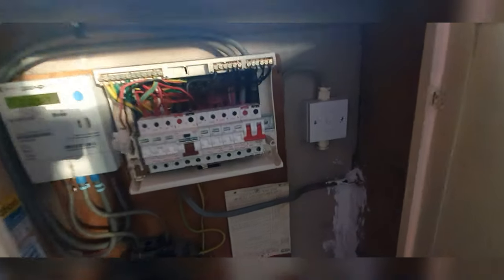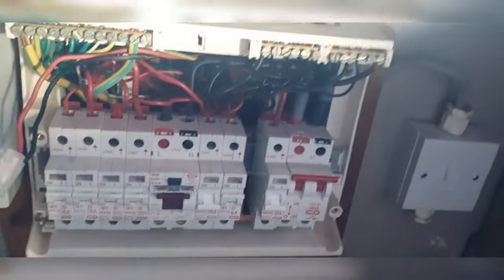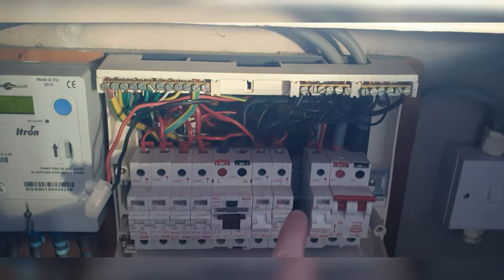There's not really much to show - that's going over there, problem solved. It's RCD protected - yay. So I've moved that over. They seem to have borrowed a neutral. I've moved that one over there now - so you've got your lights up and there's your lights down.